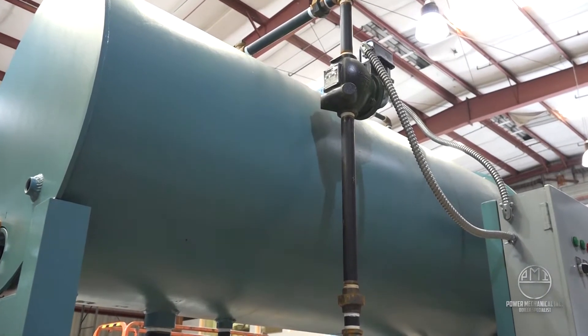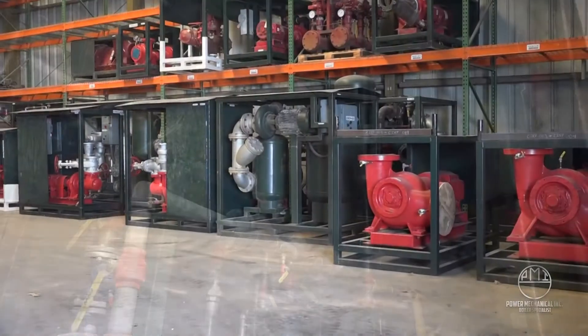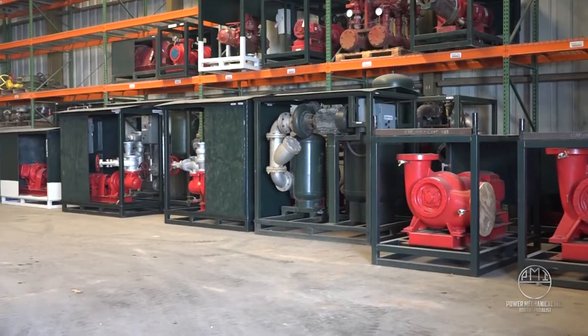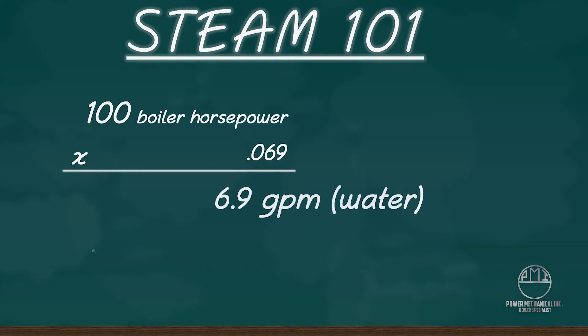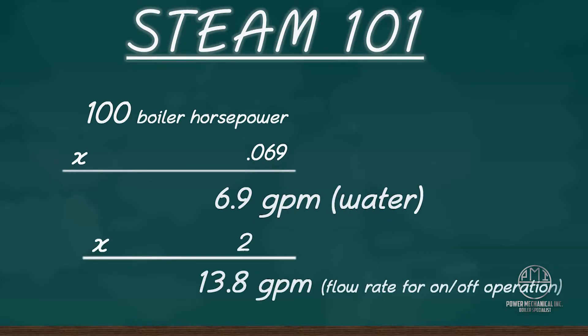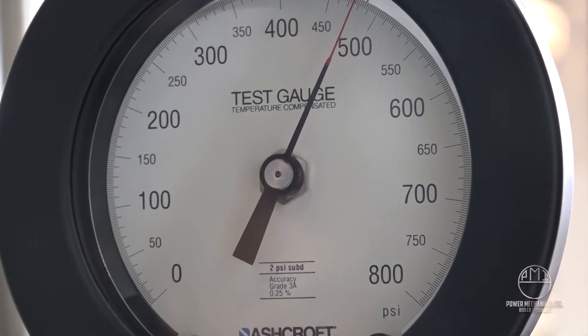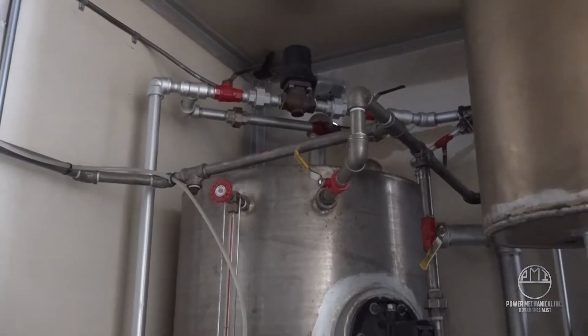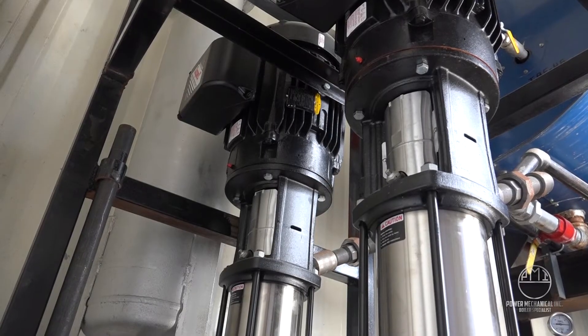Water is provided to the boiler by way of feed systems. There are many factors that go into selecting the proper feed pumps and receivers. Based on the boiler size, the general rule of thumb is to provide the boiler with twice the evaporation or steam production rate at full load. However, modulating systems, operating pressure, condensate return temperatures, and receiver sizes all affect the selection of the correct boiler feed pumps.